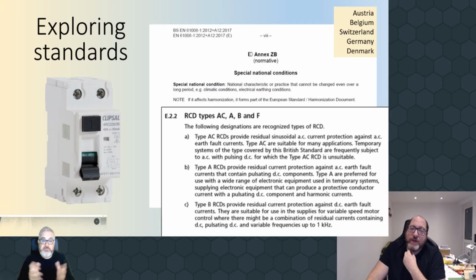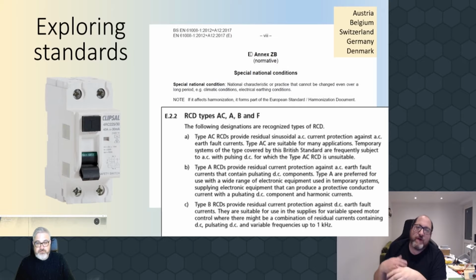I think it has to. Similarly, with regards to the knowledge of the characteristics of the equipment itself, when we come to look at the 18th edition, we talk about division of installation, unwanted tripping, no more than 30% of the current of the I delta N on an RCD.